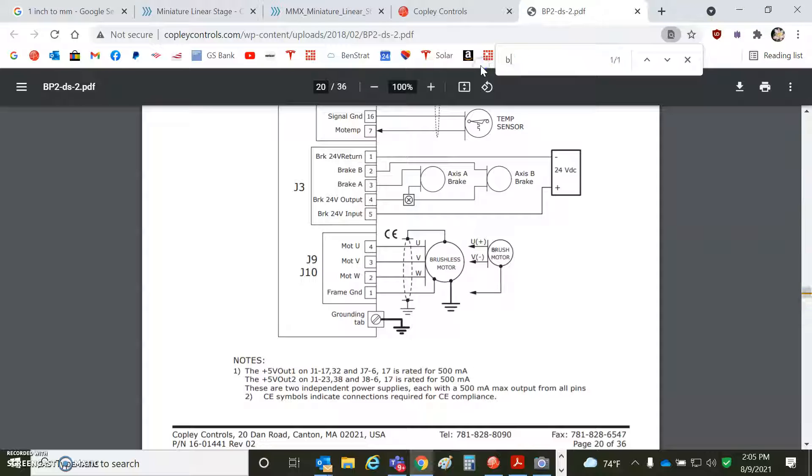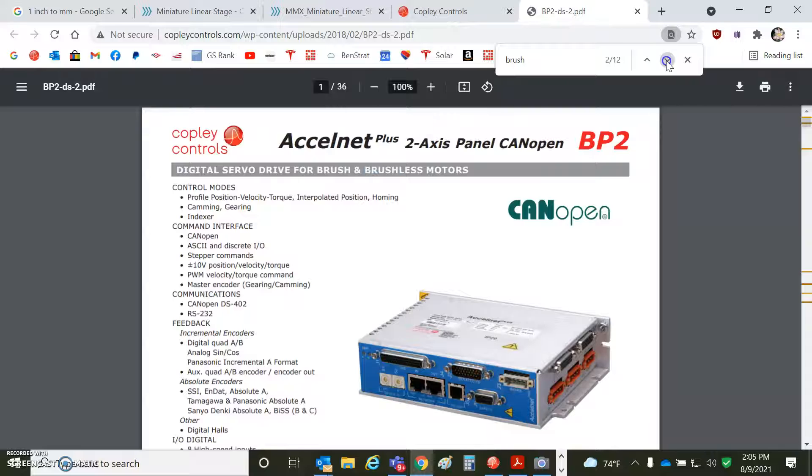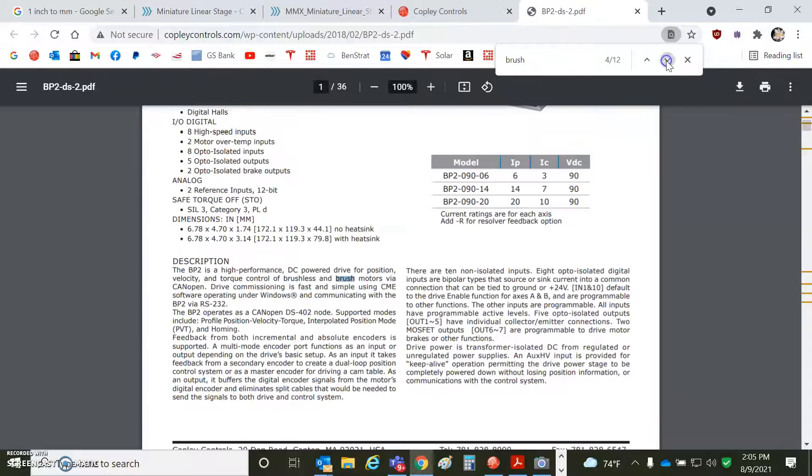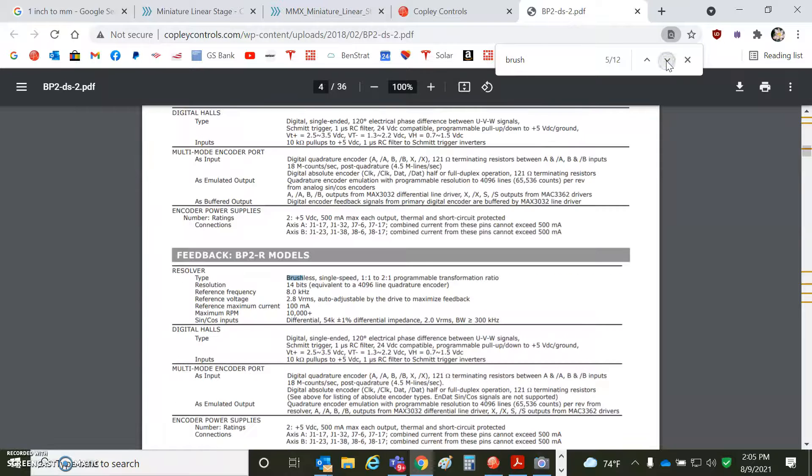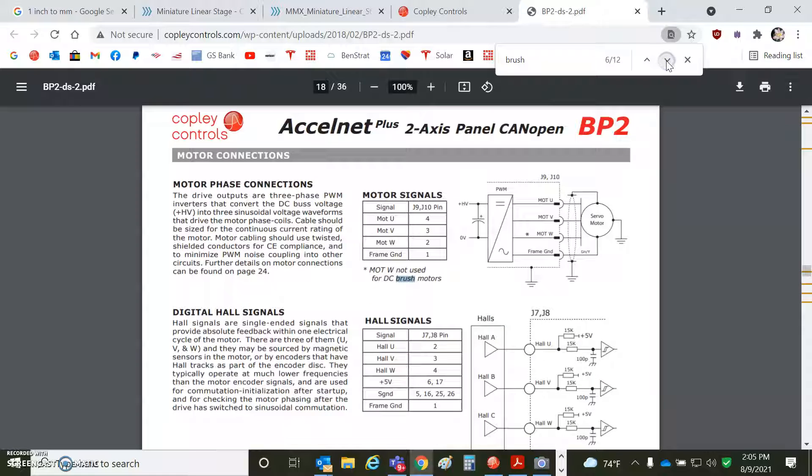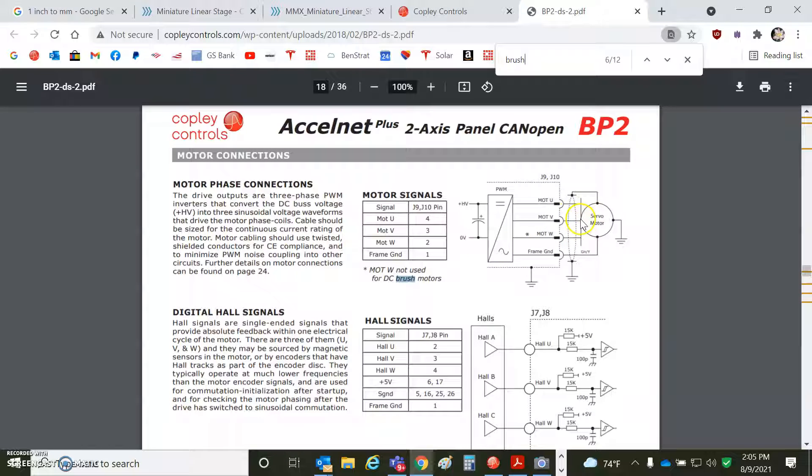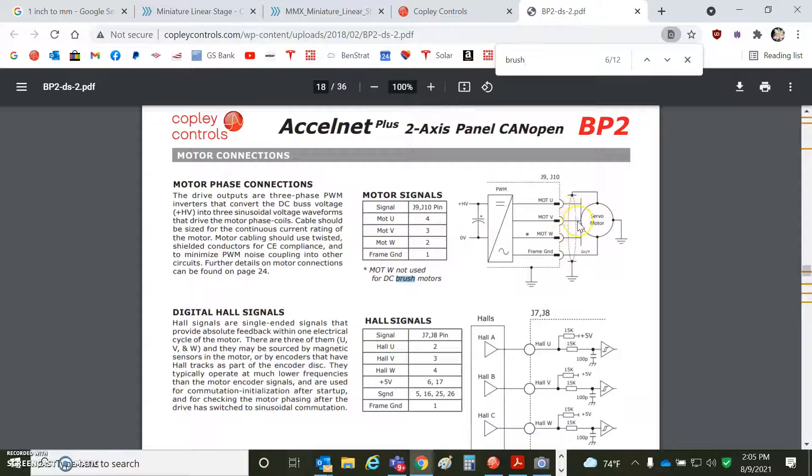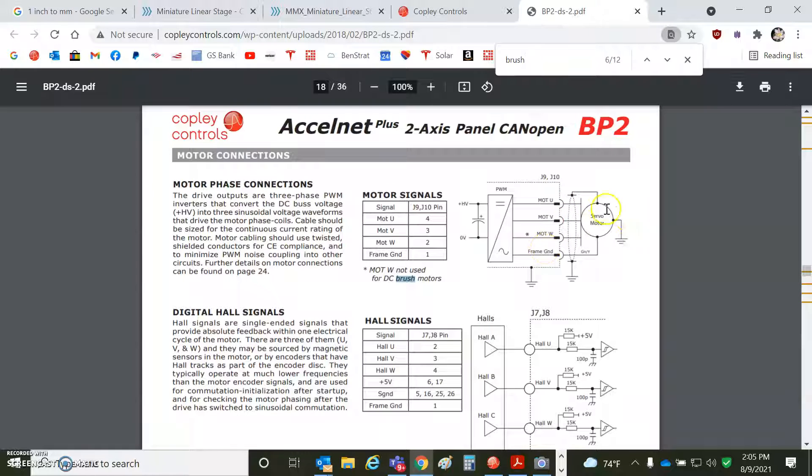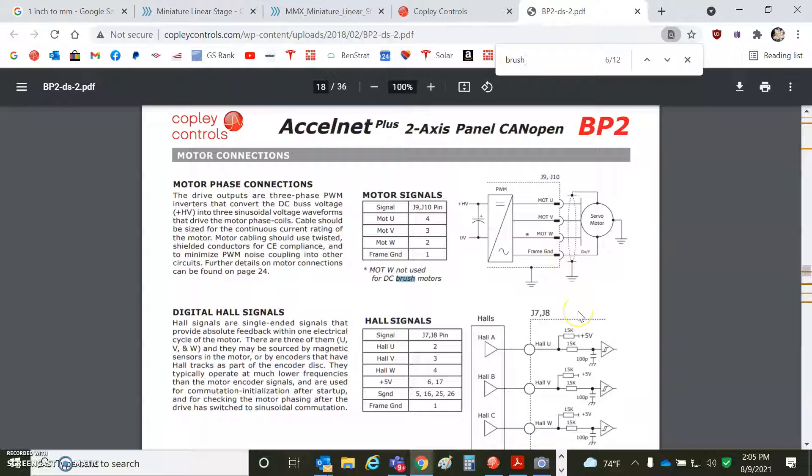There's also a brush, a way to wire up a DC brush motor. That's like a voice coil. In the data sheet, we don't say voice coil, but in the software we do. But you see this wire, you don't hook this wire up for a two-wire motor. So U and V, you connect your coil to U and V, like a brush motor. And then the case of the motor going to Earth and the shield going to Earth and the feedback shield not connected to the motor case, but finding a path to Earth.